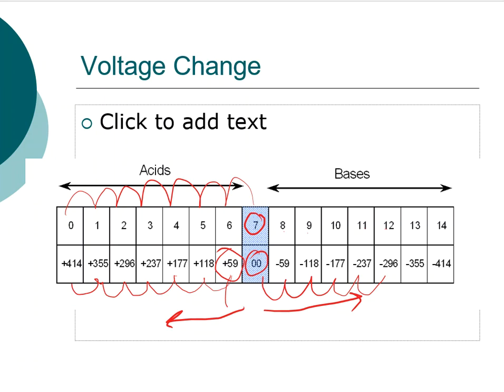On the acid side of the house, it doesn't need those. It's spitting electrons out. If it's spitting electrons out, then those electrons are free and they can go up through the wire and generate some voltage. But if we're on the base side of the house, it requires those electrons. So it's going to take those electrons from somewhere, aka reference probes in the inner workings of the ISE, and it needs them, it eats them, which makes that voltage go down, negative-wise. Folks, I'm going to say 59 on this screen, but the actual number here is 59.16 millivolts. That's the actual value. That's how many millivolts it takes to change a pH number, whether it goes more acidic or more basic. Whew, what a doozy.